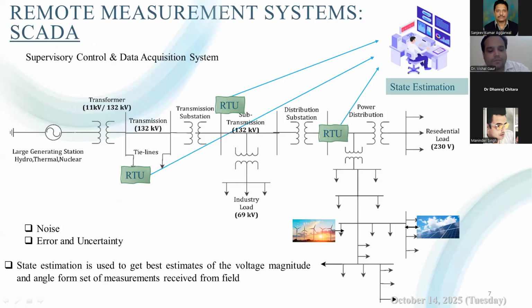So you can observe that remote terminal units are installed in the substation and act as local data collectors. They gather signals from sensors like voltage, current, breaker positions, and alarms. They then convert these into digital form and send them forward. All of these RTUs are connected to a SCADA master station through a communication network. The communication can be through fiber optics or the earlier technique, power line carrier. This ensures even remote stations can send their data to the central control room.